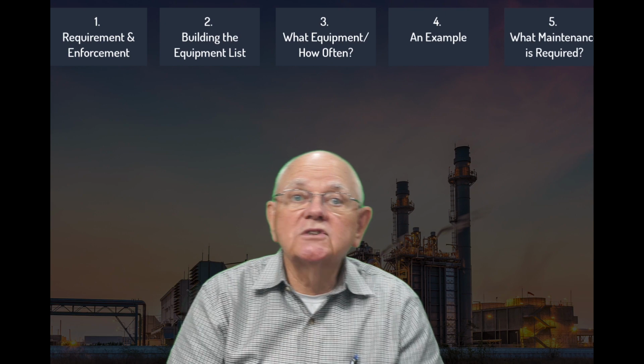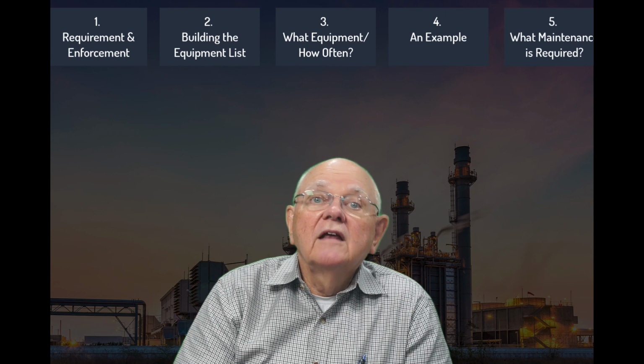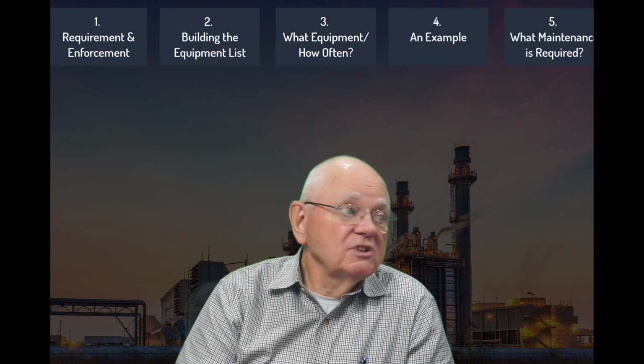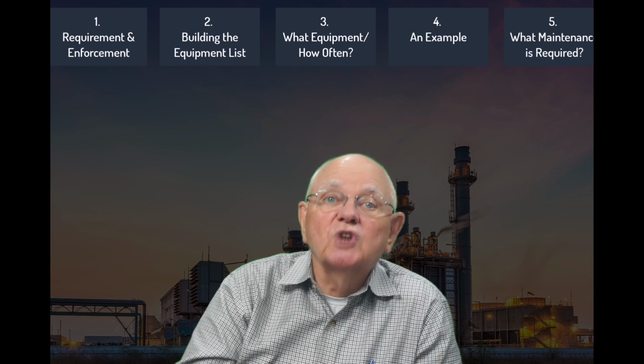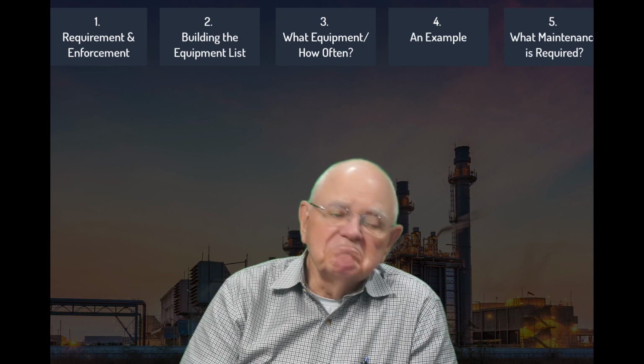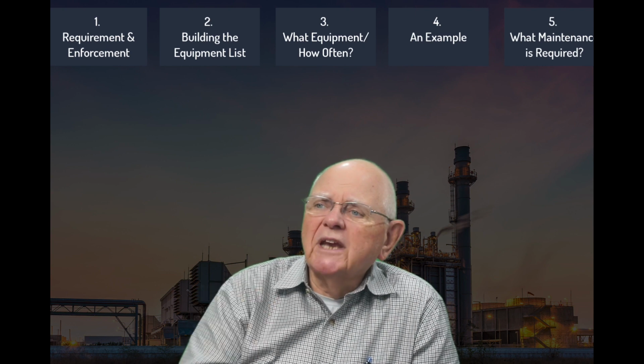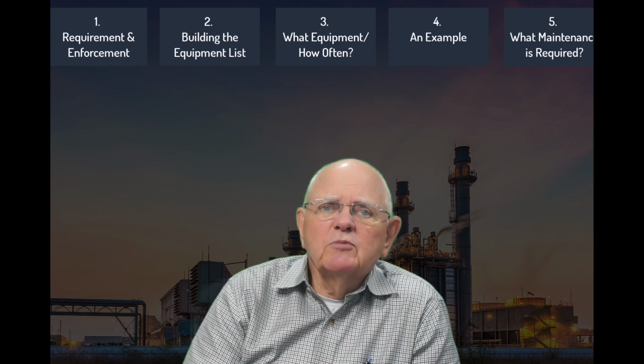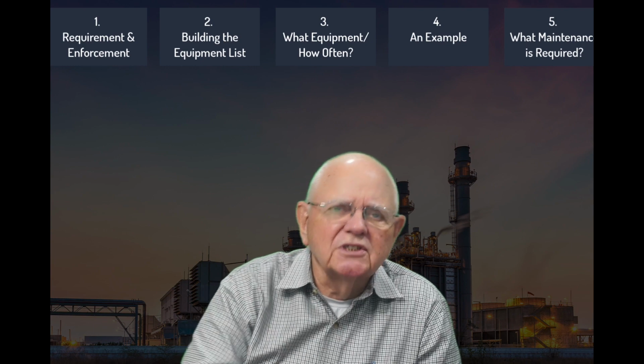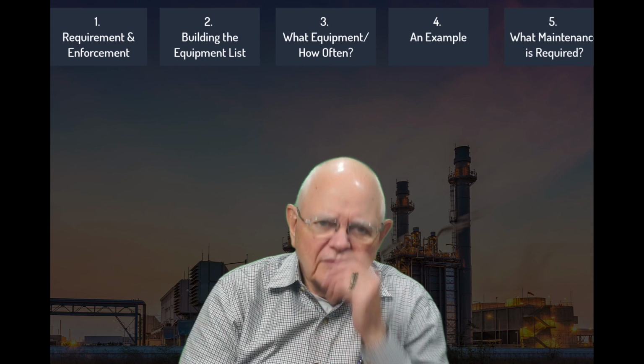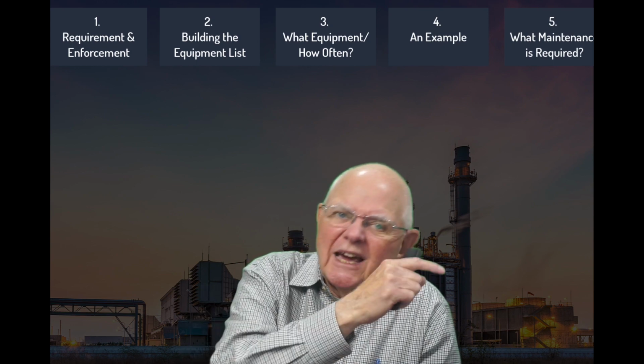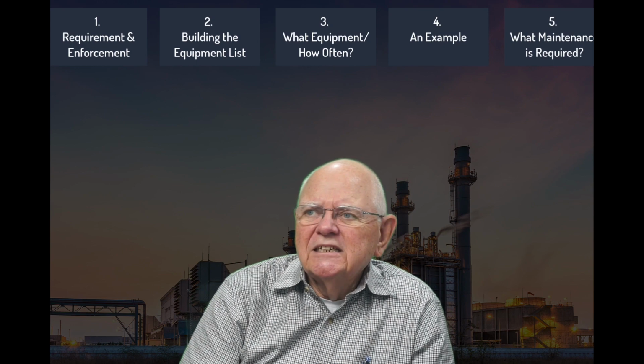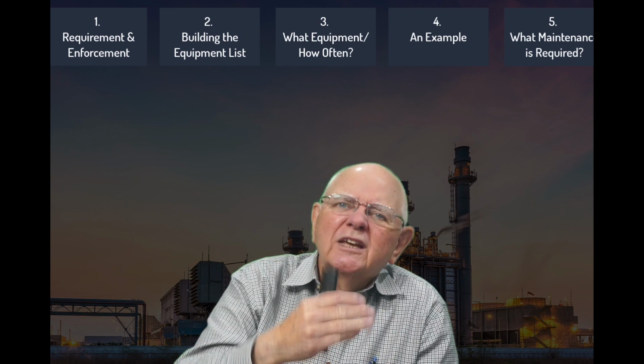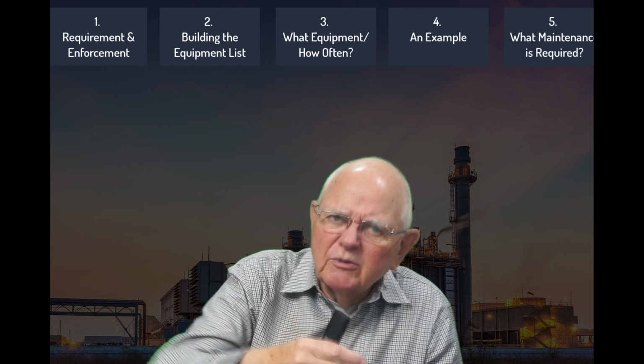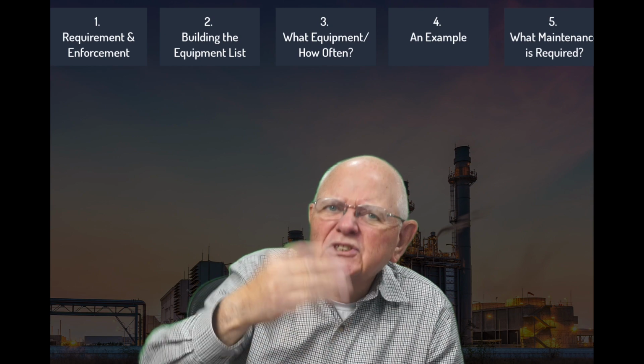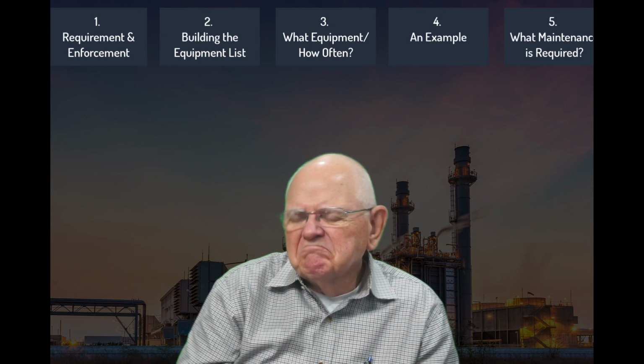Looking at the physical condition, that transformer is pretty much almost like new, though it's been in service a while and doing good. I looked at all the maintenance data, insulation resistance and so forth, and it's been in pretty good shape. However, we did miss the last maintenance cycle on it, so instead of assigning it a 1, I'm going to assign it a 2. We're going to step up the maintenance on it a little bit.